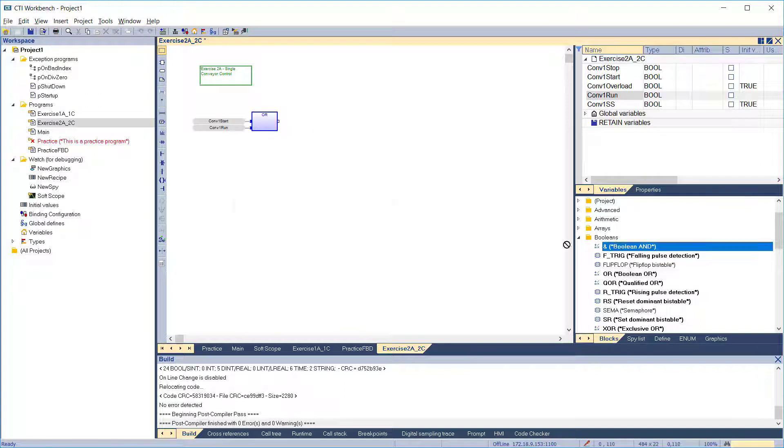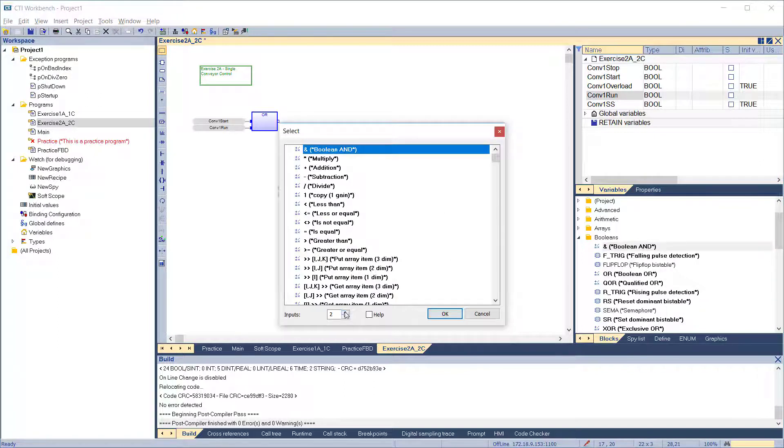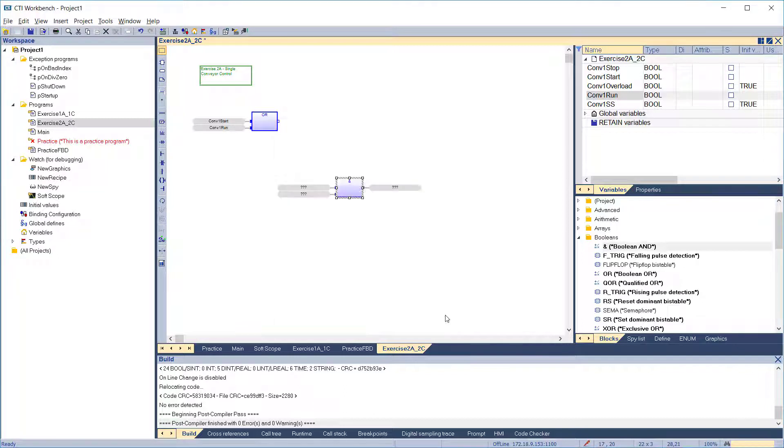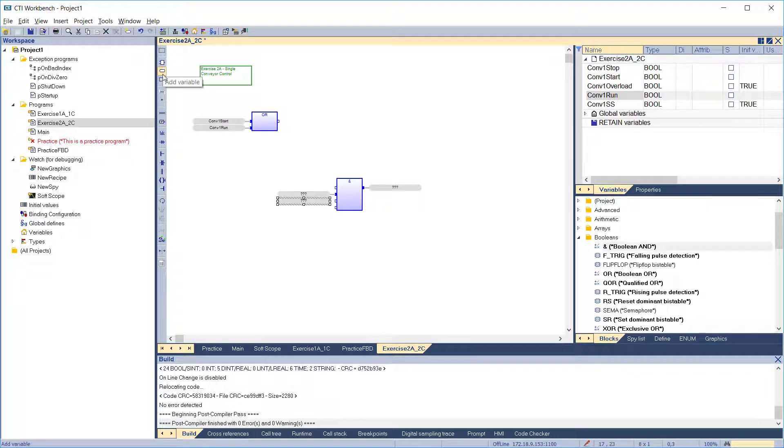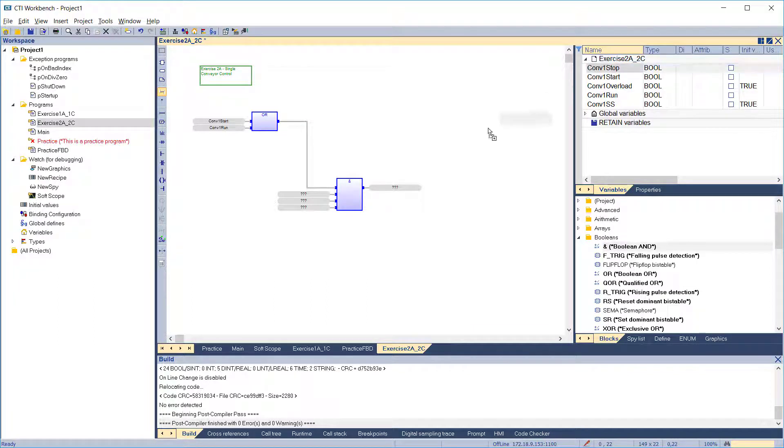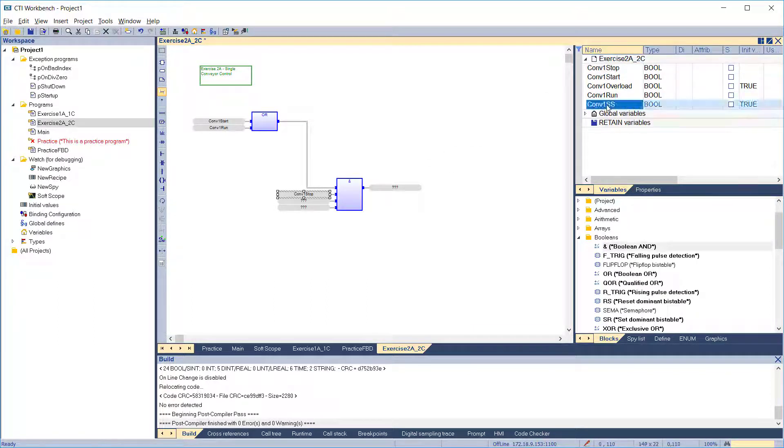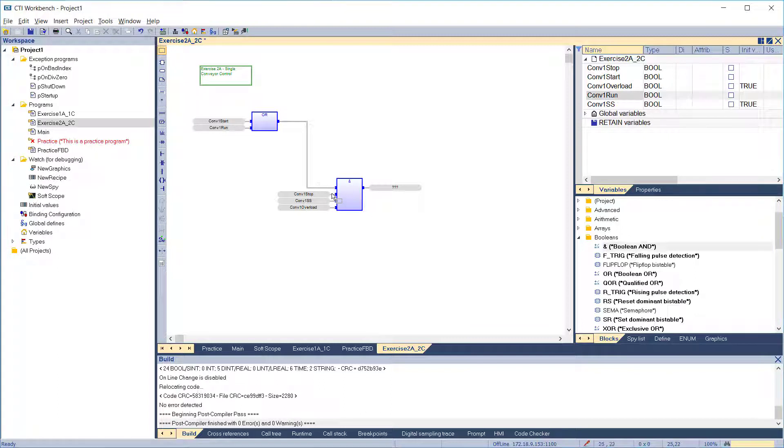Then add the boolean AND function. Give it 3 inputs. Insert variable blocks for the added pins. Connect the variable blocks to the function and connect the output of one function to the input of the other. Attach variables conveyor 1 start, conveyor 1 safety stop, and conveyor 1 overload. Then we have to negate the stop input. And conveyor 1 run to the output.